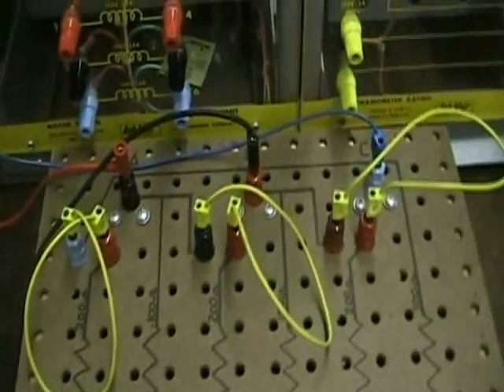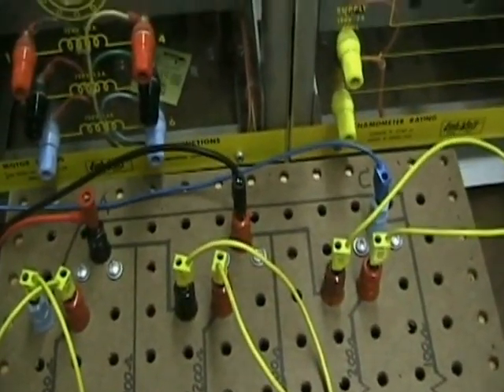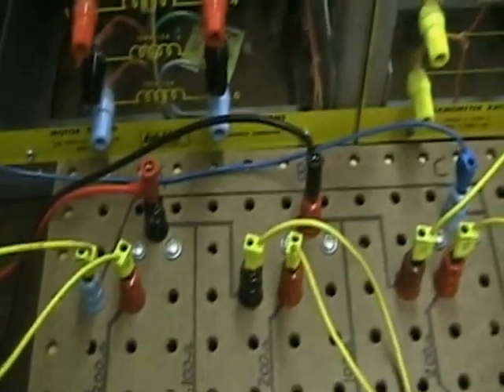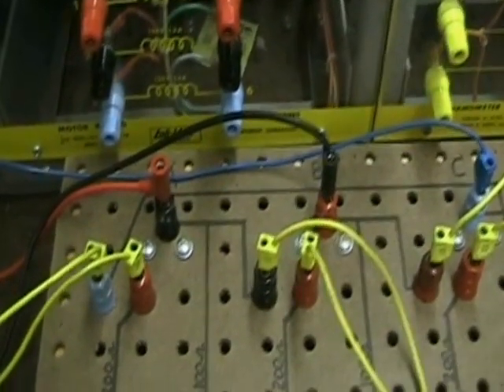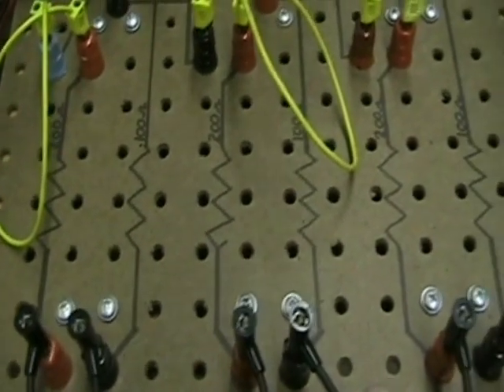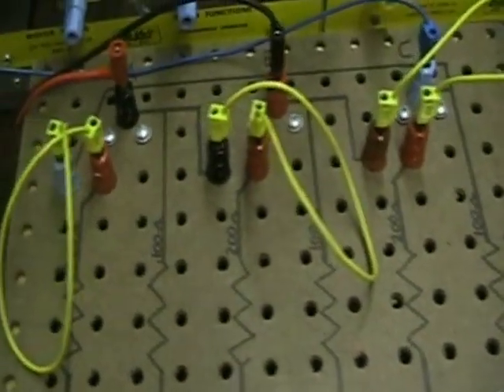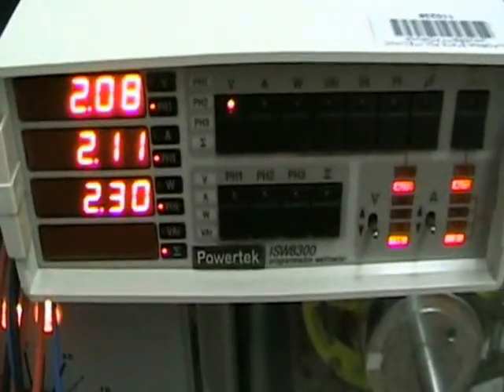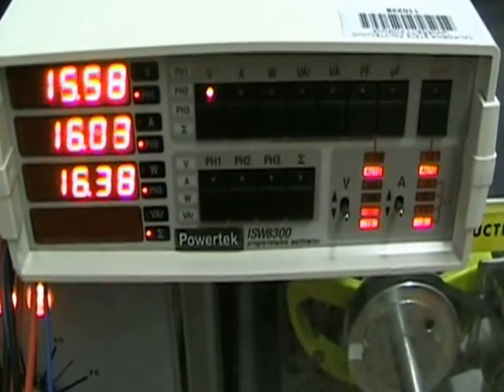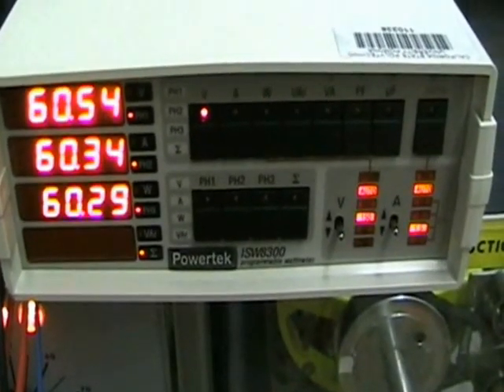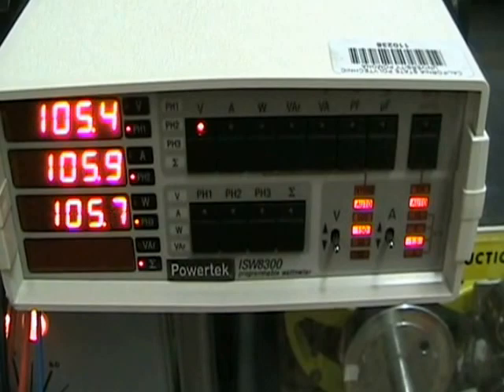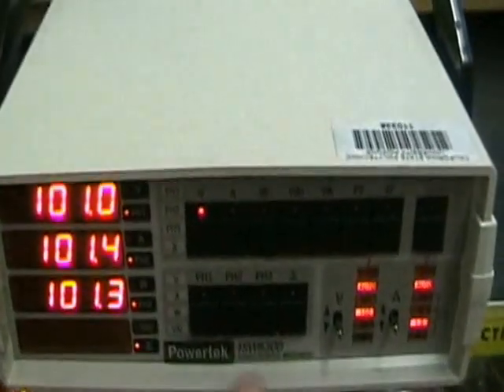The balanced delta circuit of 300 ohm loads is created simply by interconnecting the phases with these jumper wires and connecting the 100 and 200 ohms in series for each phase. Again, apply the voltage and energize to the desired voltage reference. In this case, 100 volts is a convenient number.